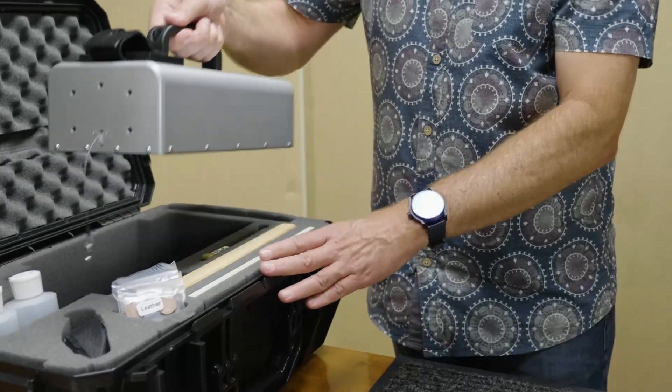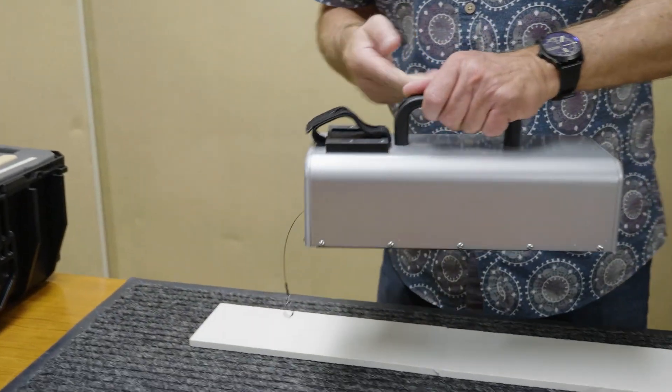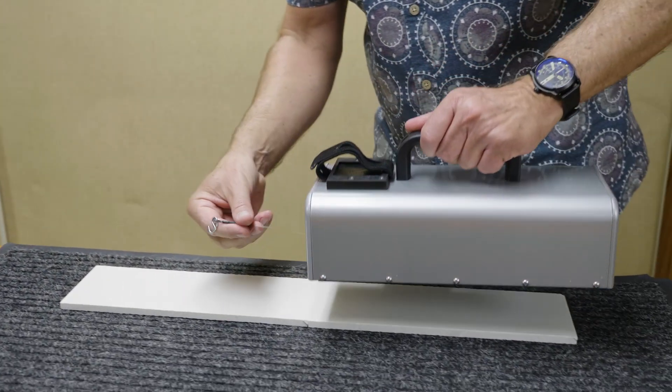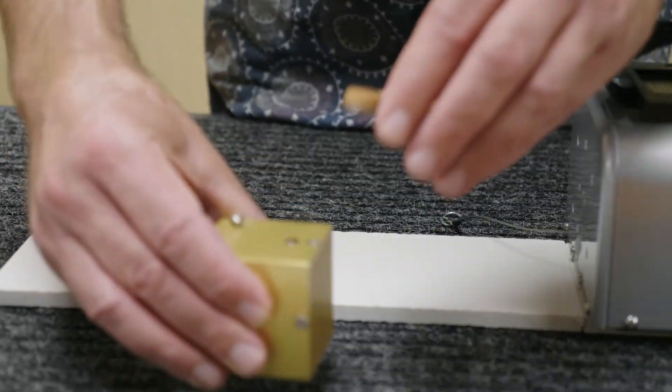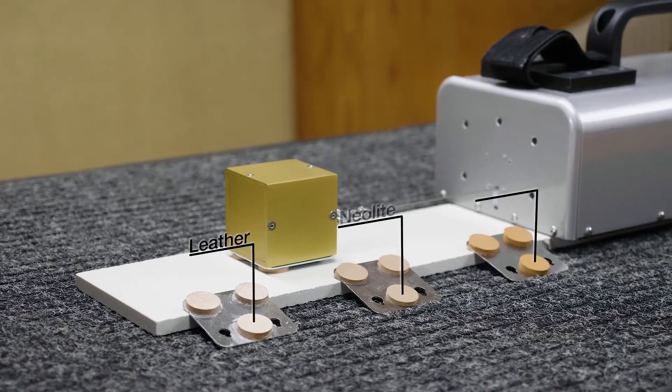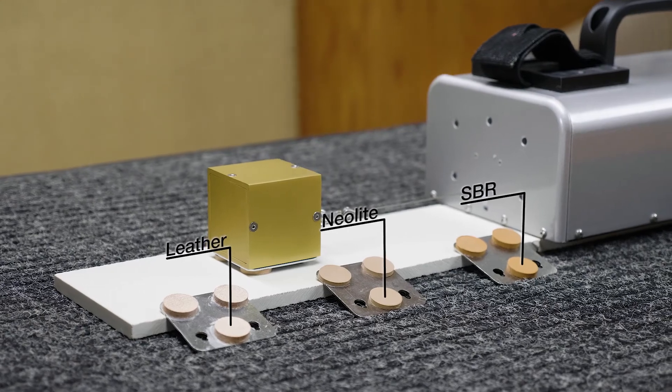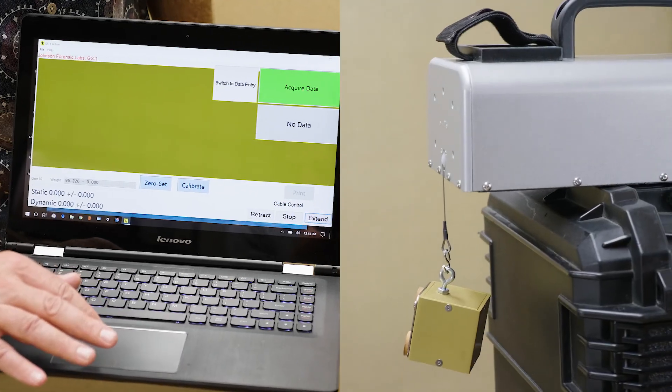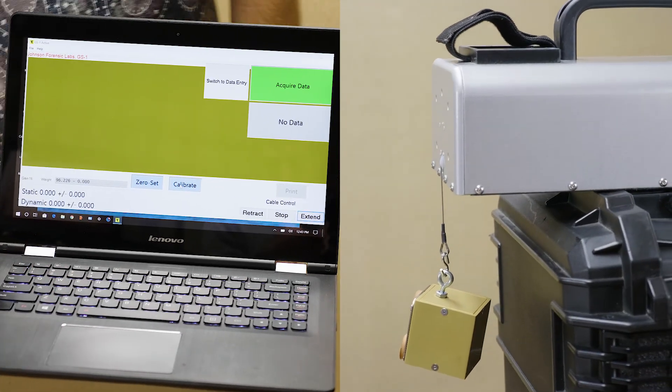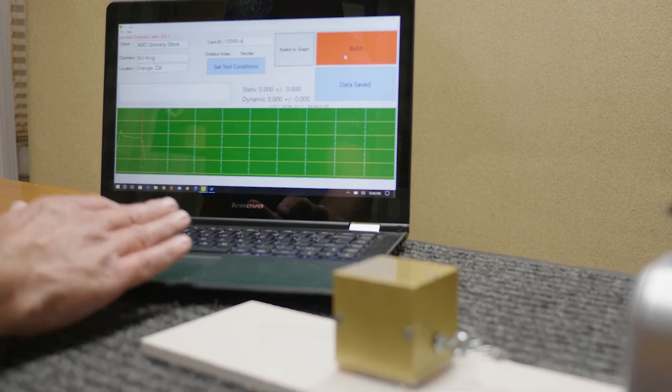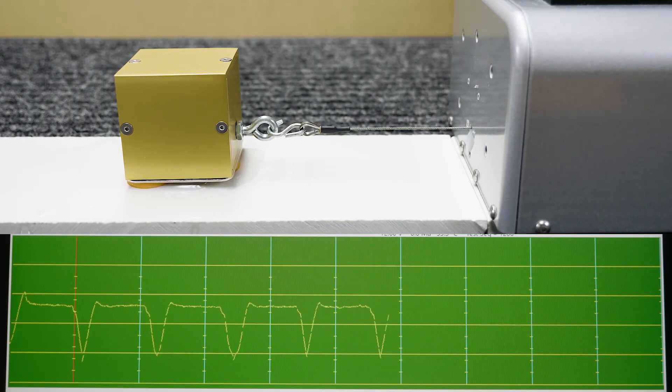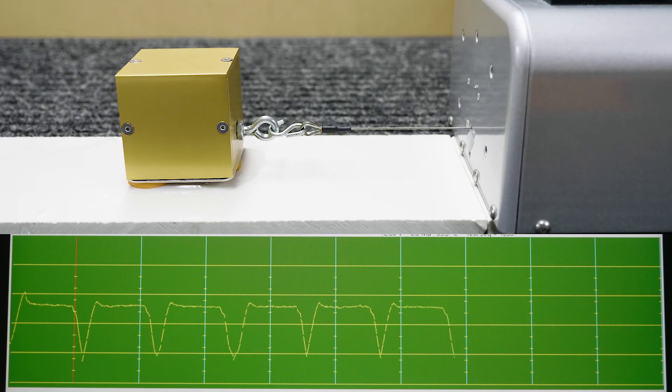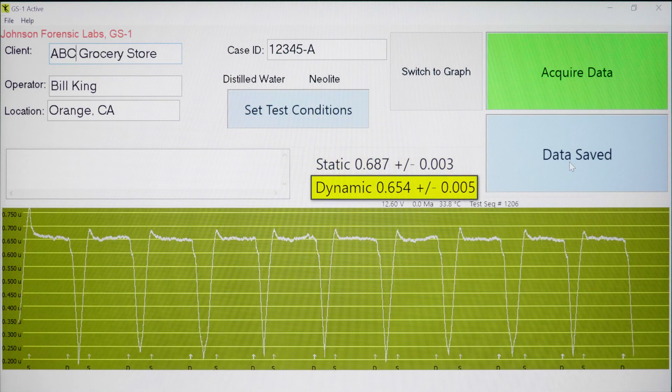The GS1 is a specially designed portable instrument called a tribometer that measures forces to a high precision. It can probe any solid surface using a special shoe surface. After a quick and simple calibration process, the GS1 will take 10 successive measurements and automatically compute and display the force ratio, S-coff and D-coff.